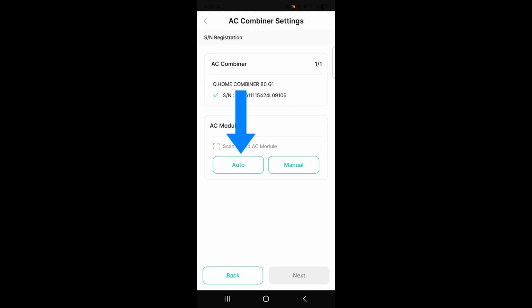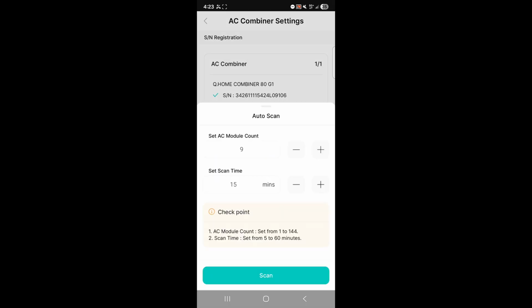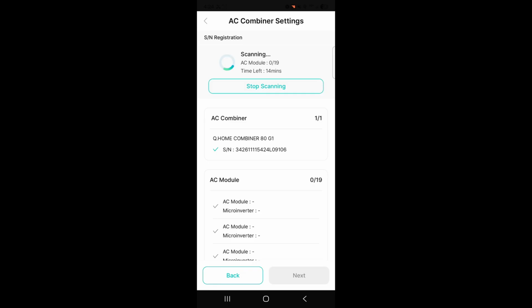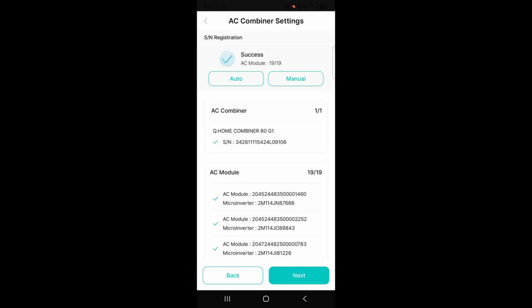Select Auto to perform an auto scan of the microinverter serial numbers, or select Manual to scan each microinverter serial number manually. When performing the auto scan, make sure the correct number of microinverters is entered and select the scan duration. The scan process can take several minutes. Once the scan is complete, verify the correct number of AC modules has been scanned and select Next.